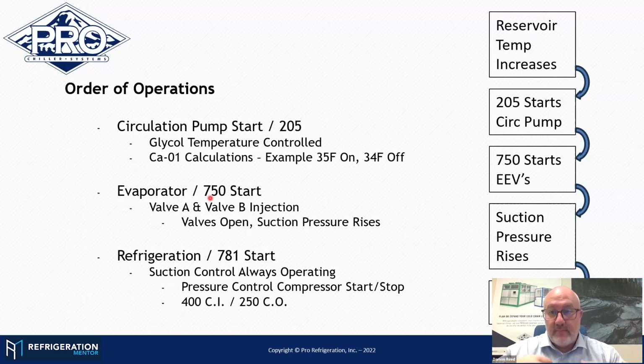The next thing that is expected to happen is my suction pressure is going to rise. As my suction pressure rises, my 781, which is always monitoring that, my refrigeration controller, says, hey, suction pressure is coming up, and it waits to start a compressor. If that suction pressure gets to 400 or above, then it goes ahead and starts a compressor. I mentioned earlier that our Pro Green system has 250 horsepower compressors. They're in parallel, they're both VFD controlled. We're not going to start both compressors at the same time. We're only going to start one.